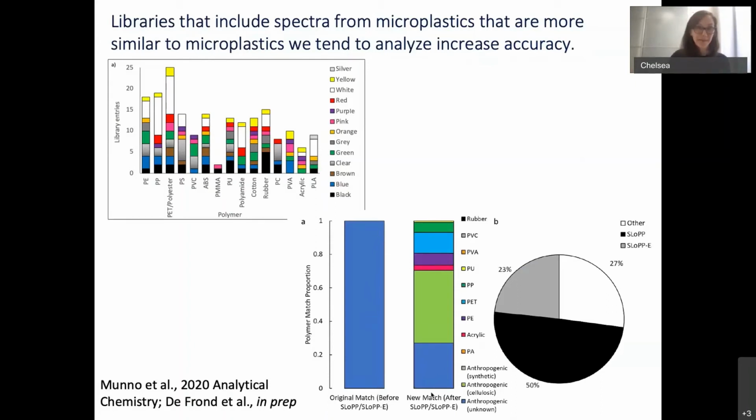SloPP-E is just the environmental particles within our instrumentation, set up on our Raman. And here we find that now we have fewer particles with this unknown signal, and we're more likely to be able to tell what they are. And we often get our own libraries popping up over the other libraries. Now for FTIR, this isn't out yet, we're still working on it, but in our lab, as we start to use FLOP, we're finding a similar thing, particularly for pesky particles like tire wear rubber.